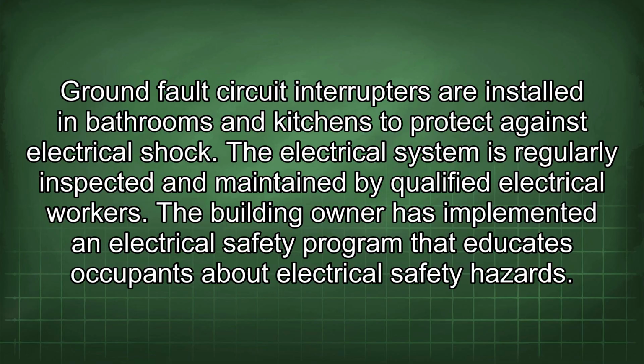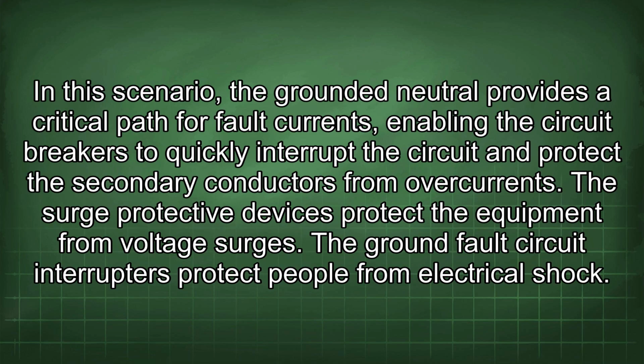The electrical system is regularly inspected and maintained by qualified electrical workers. The building owner has implemented an electrical safety program that educates occupants about electrical safety hazards. In this scenario, the grounded neutral provides a critical path for fault currents, enabling the circuit breakers to quickly interrupt the circuit and protect the secondary conductors from overcurrents.